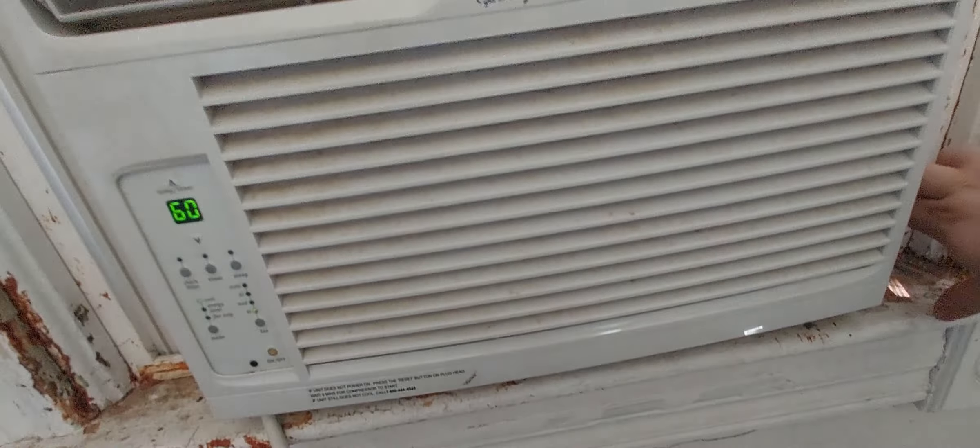I have it running on low, because that's the quickest rate for this thing to build head pressure. It's been sitting a while — it's got to get the juices flowing. And I checked the hot coil, the outside coil, the condenser — it is red hot.